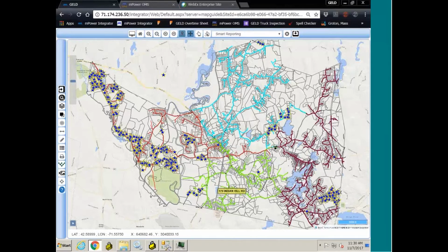By 5 o'clock in the morning, we were down to, well, these 3 had still been ignored, but the crews got these 2 big outages dealt with right away, and then these 2 medium outages were just kind of getting finished up at 5 in the morning. So by sunrise, we were working on an individual transformer and individual houses. And we were able to do that and do the triage effectively because we had this data.